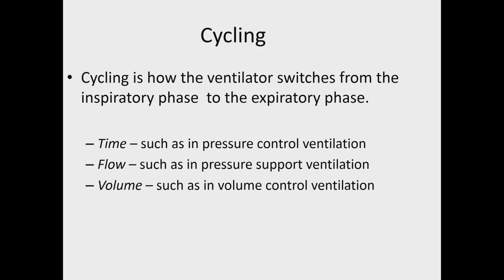Cycling, conversely, is how the ventilator switches from the inspiratory phase to the expiratory phase. Much like with triggering, it can be regulated by either time, flow, or volume. In pressure control ventilation, time simply means that after a certain period of the inspiratory phase, the ventilator will cycle to the expiratory phase.